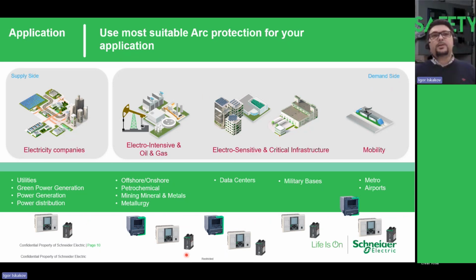Okay, electro-intensive. This application is possible, but usually the customer chooses built-in arc flash protection and protection relays. But if they use our competitor's protection relay, they have the possibility to choose our protection relays, our systems, and it brings a more efficient arc flash protection. Data centers also, that's not a huge difference.